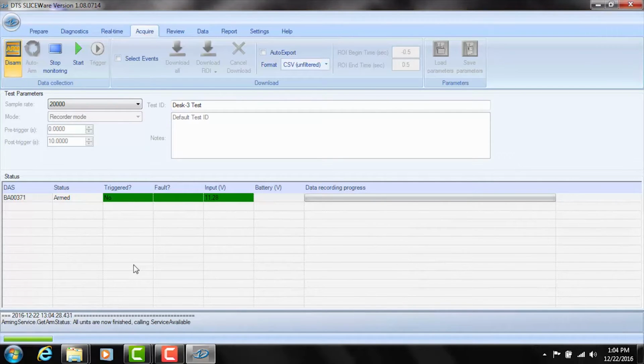At that point, it's waiting for a trigger, so you might have a switch connected to the down port on the base to initiate a start-stop command to start the recording. Or you could also have set up the system to trigger off of a level on a transducer. So if some threshold in the transducer is exceeded and you predefine what that level is in Sliceware, you can handle the triggering that way to initiate the 10-second recording.